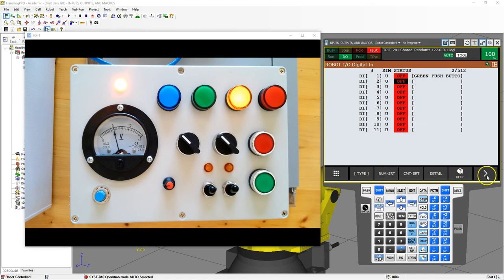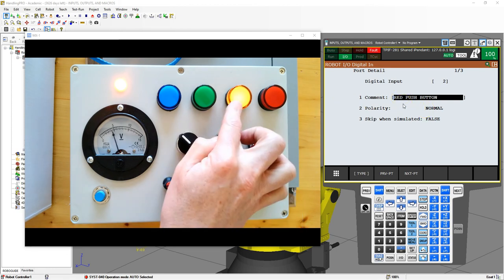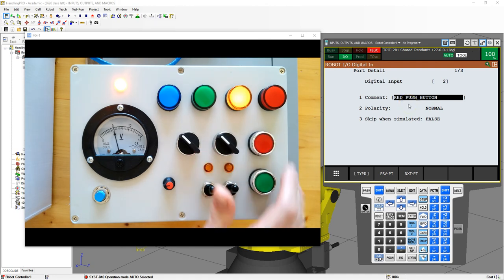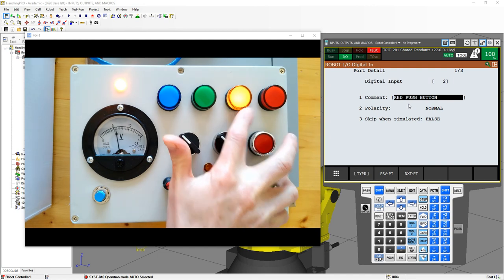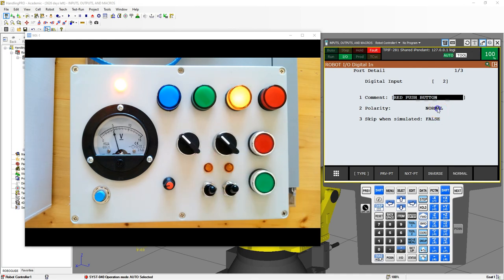Let's go to digital input 2 as our red push button. We can go to detail and name it 'red push button.' Red push button — notice the light is actually on, so if I press it, this has an opposite polarity. This is a normally closed device, whereas the green push button is a normally open device. Normally open means in its normal state there's no electricity going through, and when I press it, there is electricity. Normally closed means with it not depressed, electricity is flowing; as soon as I press it, electricity stops flowing. So we're going to switch the polarity of this to inverse, and we'll need to do a power off and power on to enable the polarity change.